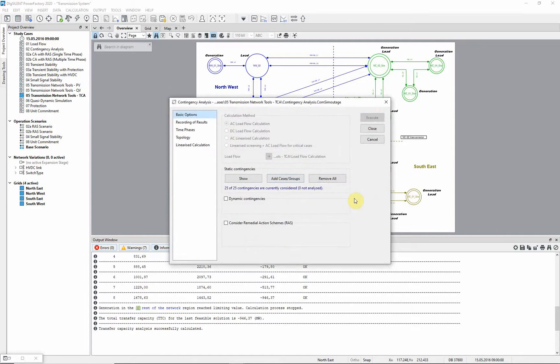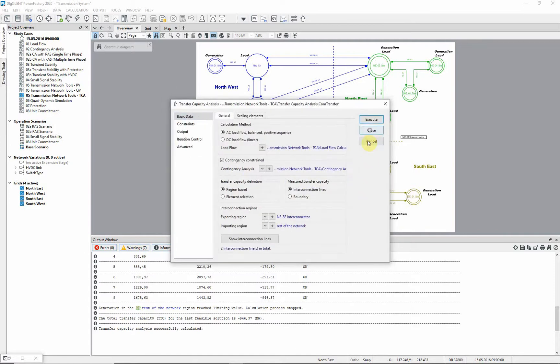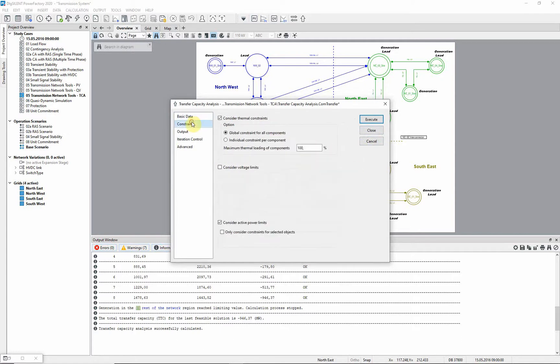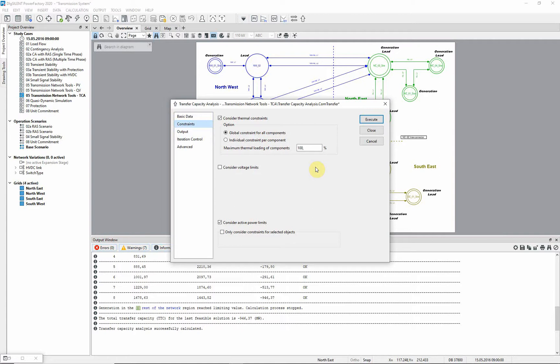In this case all the single circuit line faults have already been selected. Before executing the analysis, there is a further consideration. It is likely that elements overloaded due to faults will be able to exceed their thermal rating for a limited time, provided that post fault actions to reduce the overload are available. For this reason, we will increase the maximum thermal loading to 150%.